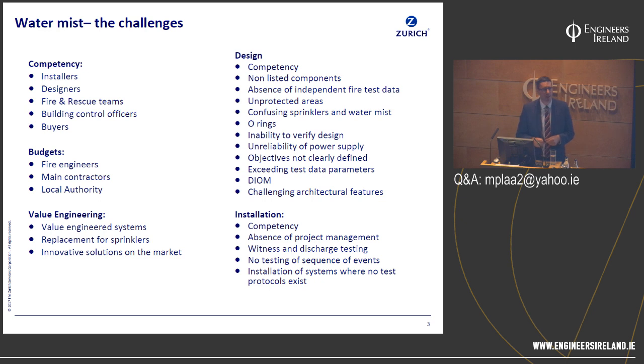And also, one of the big issues we have within water mist systems is around challenging architectural features. If you look at the sprinkler rules, there's clear guidance about what we do about sloped ceilings, obstructions, egg crate ceilings, beams and bays, circular ducting, rectangular ducting. All of these challenging architectural features we commonly find in buildings. When I come across water mist projects, I find in design manuals no reference to how we deal with all these challenges. It can often just be guesswork. So there's no real history or provenance about dealing with challenging architectural features in the building. So if we've got egg crate ceilings, sloped ceilings, obstructions in the way, be challenging and ask, where is the design information to support what I do with my water mist nozzles?